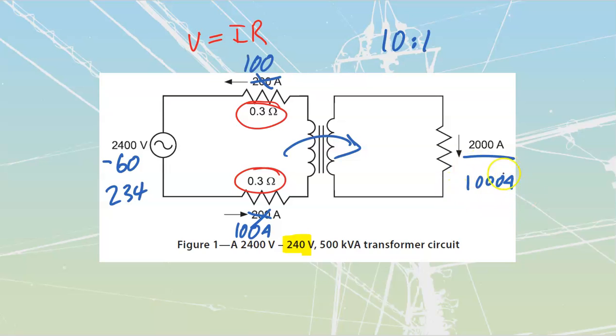So we see that during the winter, during an unloaded season, as we would normally call this, we're going to be sitting with a higher voltage. But then as we load up inside of here, we would start to drop that terminal value of voltage. There are going to be customers, some of you are going to run into, that are going to run seasonal types of loads.